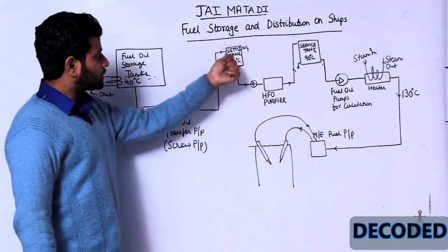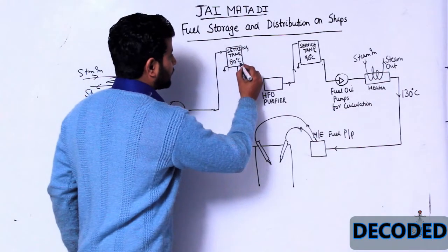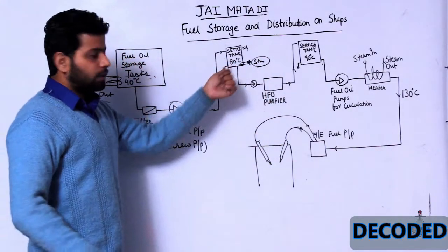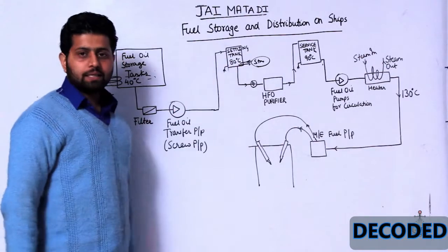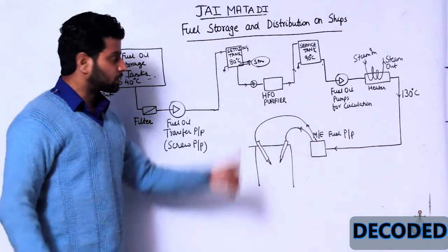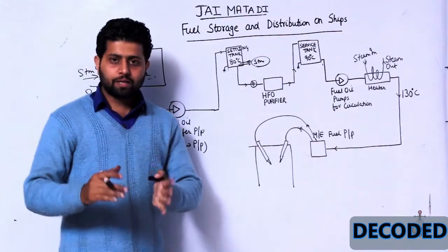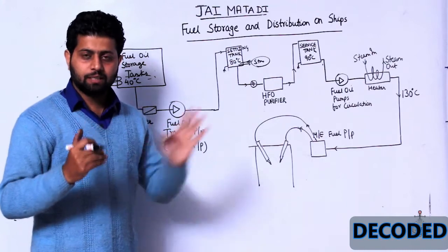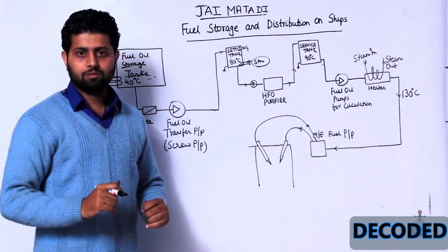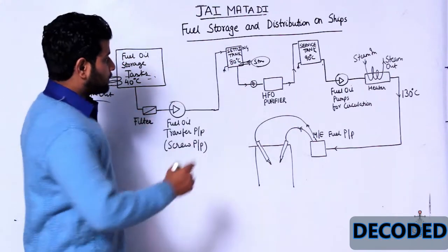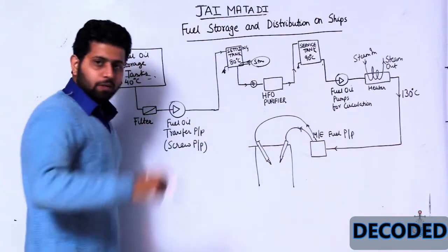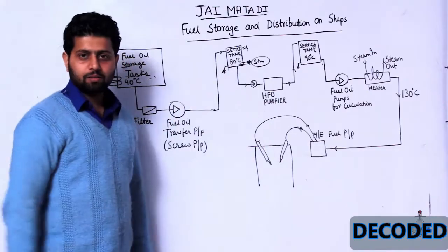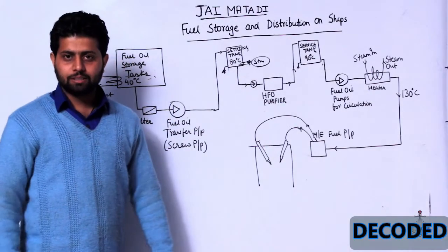From the storage tank, a fuel oil transfer pump — which is a screw pump — takes suction and pushes oil through the filter into the settling tank. In the settling tank, steam in and steam out heats the fuel oil up to 80 degrees centigrade. It is called a settling tank because all the dirt particles, dirty things, and even water — which is heavier than oil — settle down. We open a drain to remove the water and sediments, so a kind of separation is taking place.